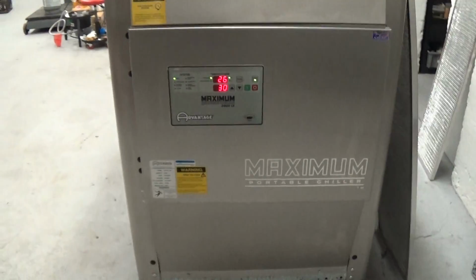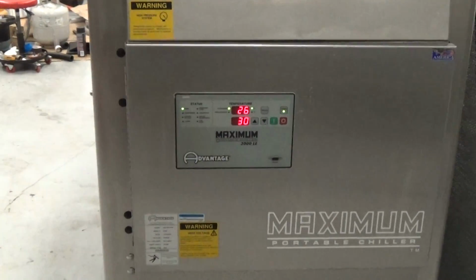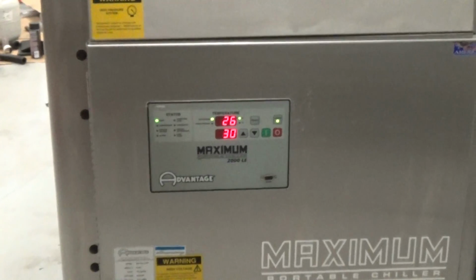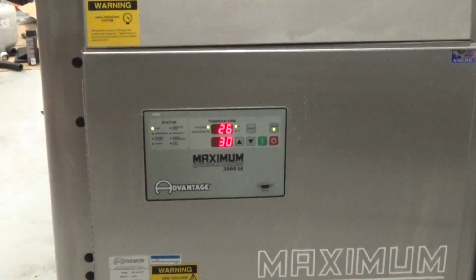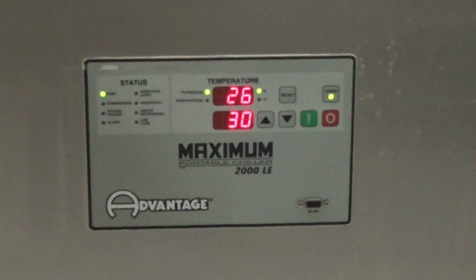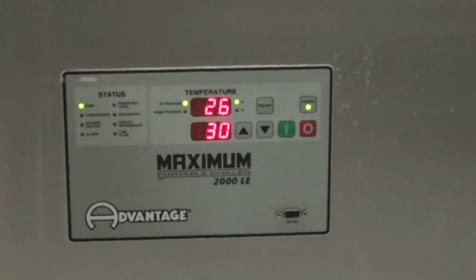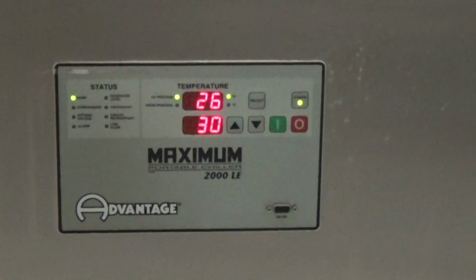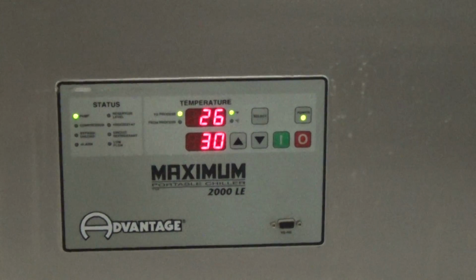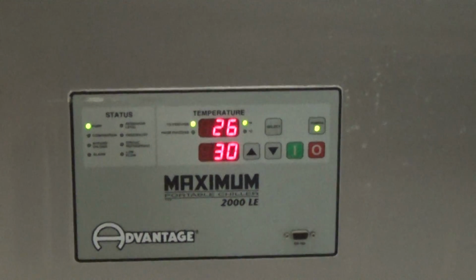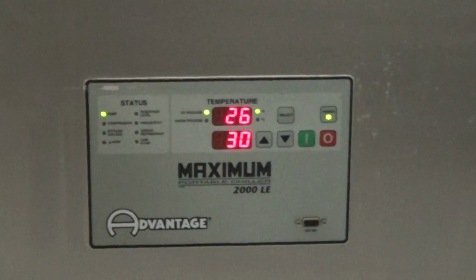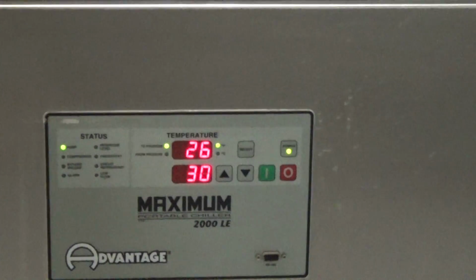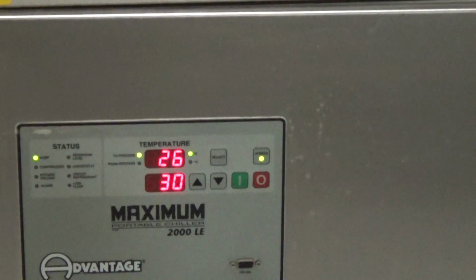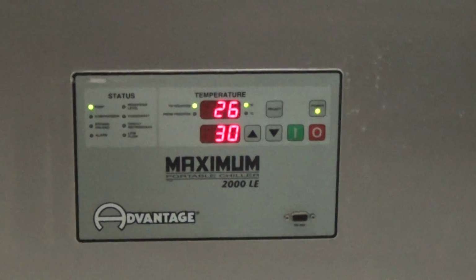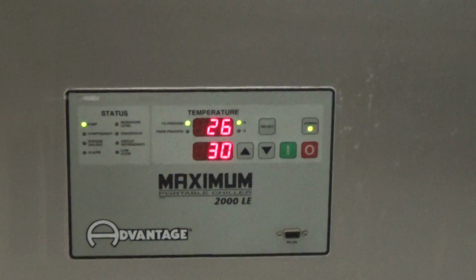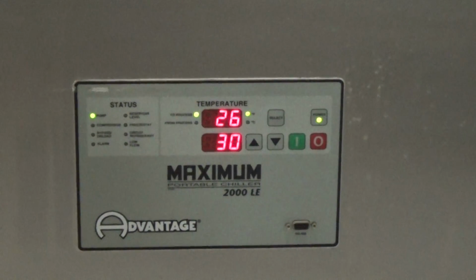Lastly, I just want to mention probably a 50% glycol mix. When you are chilling down to temperatures like this, a 30-degree set point, there are points in that evaporator slash heat exchanger that are getting down between 30 and 40 degrees less than that. So the fluids in there are seeing temperatures in that 0 degrees F to minus 10 F range. It's for that reason that the freeze protection of the mixture that you put in there is most critical.